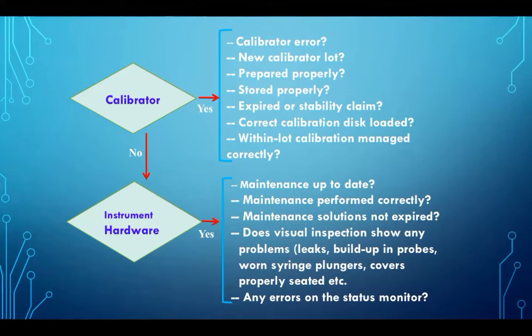And these days, we have accuracy controls also. So you can use this calibrator material as accuracy control and you can check variation. If this variation, whatever you are defining, is more than that, that is, it is significant, then do the root cause analysis. And if required, you can use this to develop your calibration schedule. Whenever it is showing more than this variation, and there is no other factor responsible, we will recalibrate.